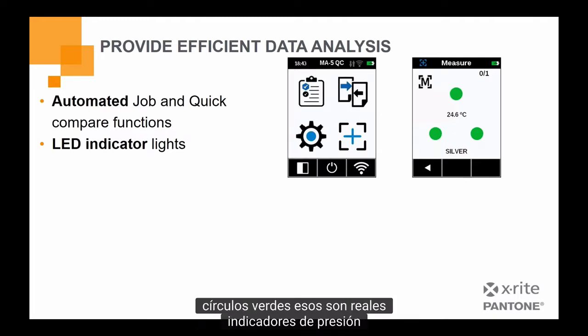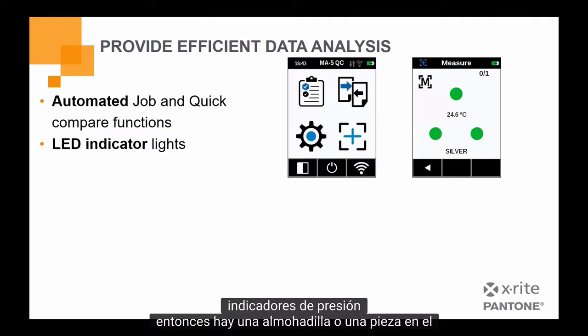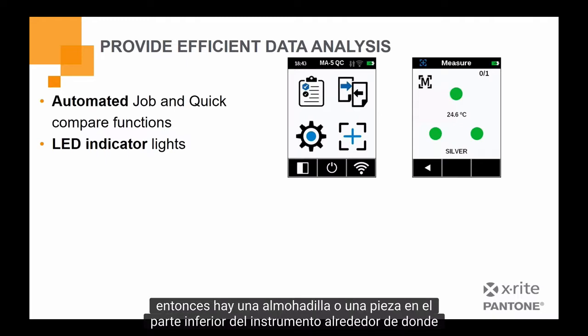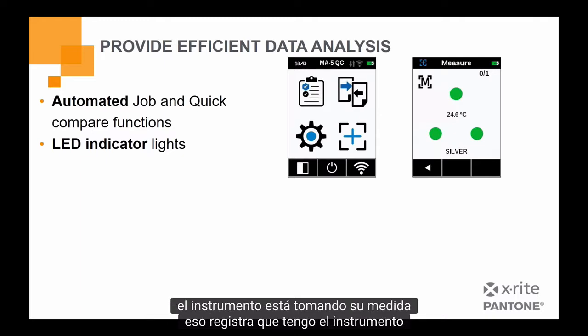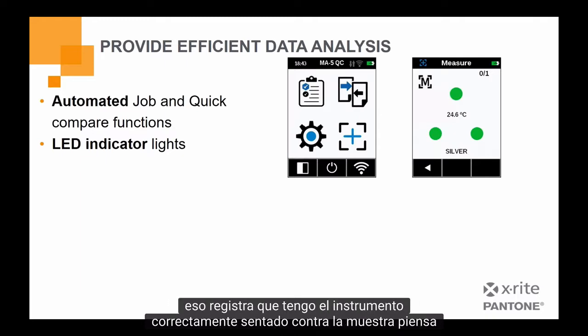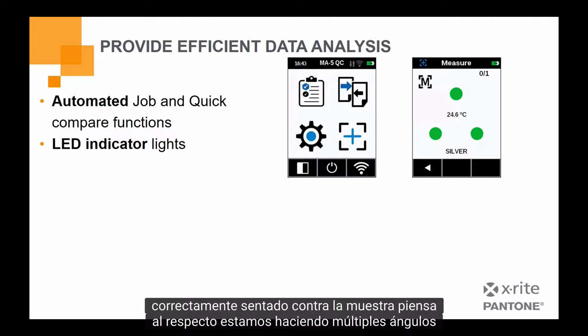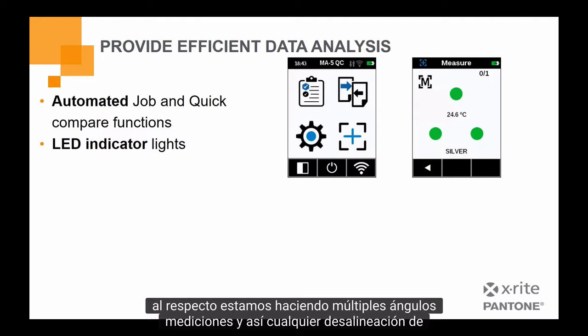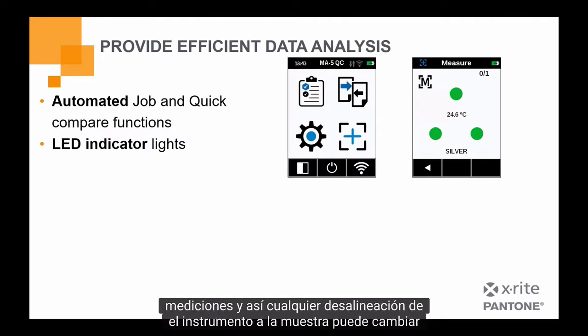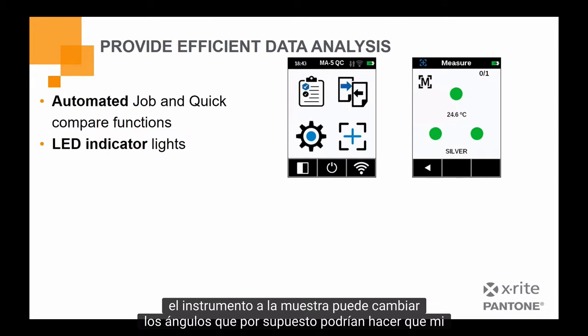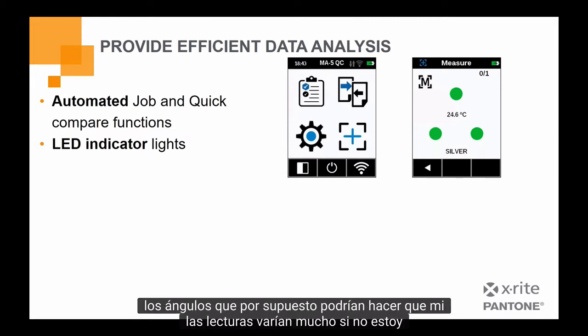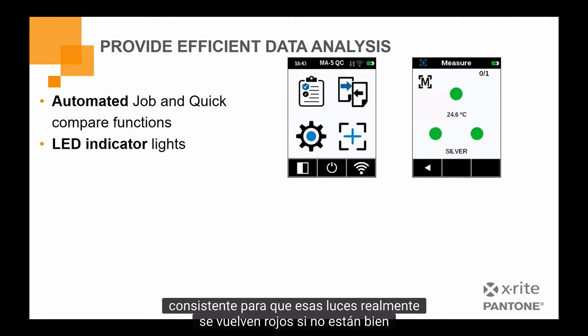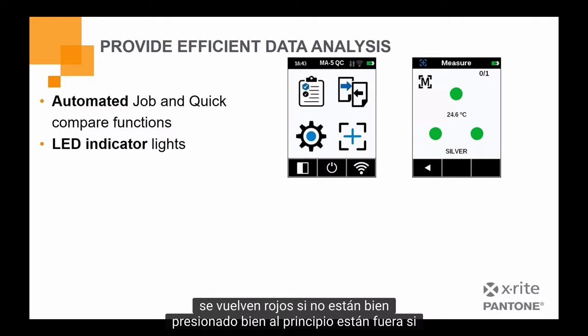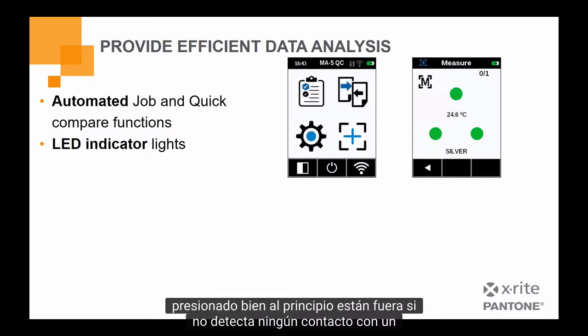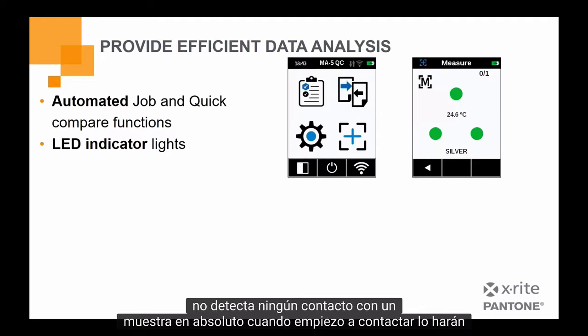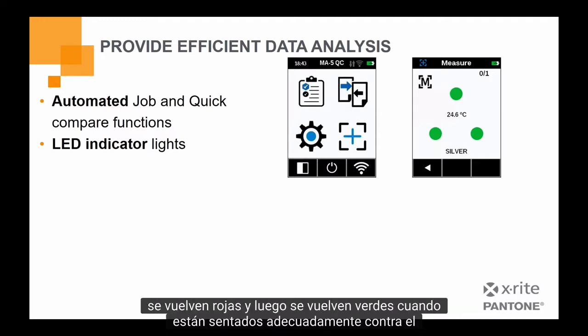indicators of pressure. So there is a pad or a piece on the bottom of the instrument around where the instrument is taking its measurement that records that I have the instrument properly seated against the sample. If you think about it, we're doing multi-angle measurements, and so any misalignment of the instrument to the sample can change the angles, which of course could make my readings vary greatly if I'm not consistent. So those lights will actually turn red if they aren't properly pressed. Well, at first they're off if it doesn't detect any contact with the sample at all. As I begin contact, they'll turn red, and then they turn green when they're properly seated against the sample.